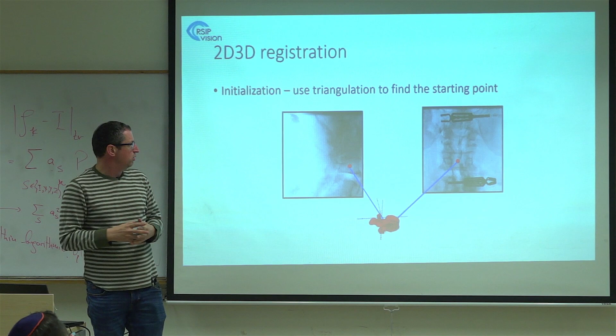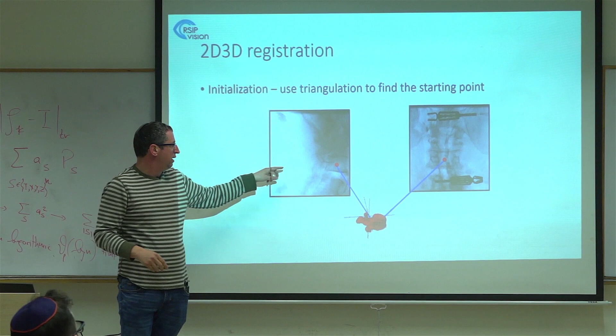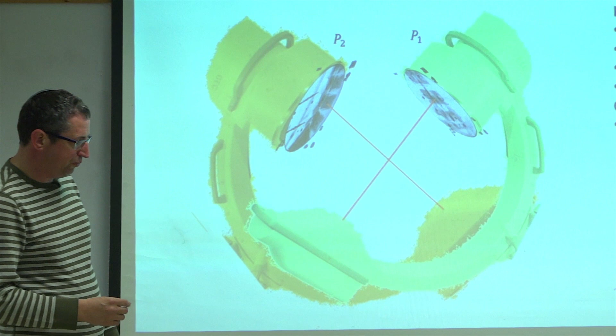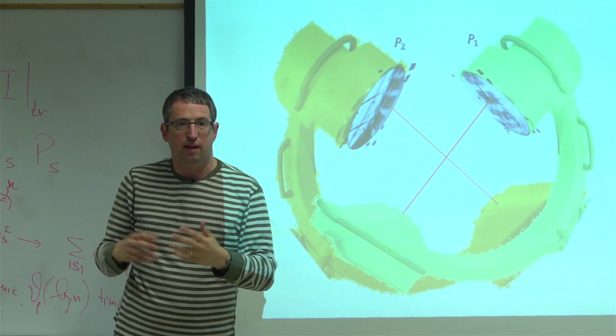So if we are talking about 2D-3D registration, we want to use triangulation to find the starting point between the 2 images. After the user performs these 2 X-ray images at 2 different angles, what you see here, we can ask him to place where the center of the vertebra is that he wants to work on, and now we can find its location in 3D. So it's going to look something like this. Here we have 2 C-arm tools, each one with a different image on it. And once we have the X-ray, we have the projection matrix, and we can now initialize registration between the 2 different coordinate systems, the coordinate system of the CT and the coordinate system of the X-ray, which is connected to the coordinate system of the world, which is the operation room. So this is the way we connect between the two different coordinate systems.